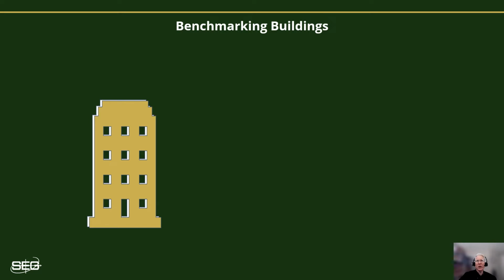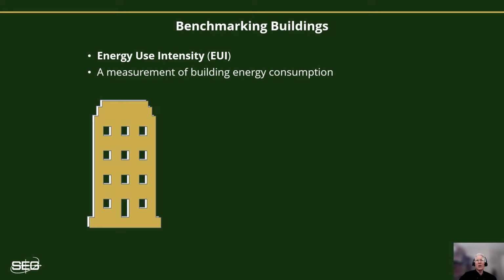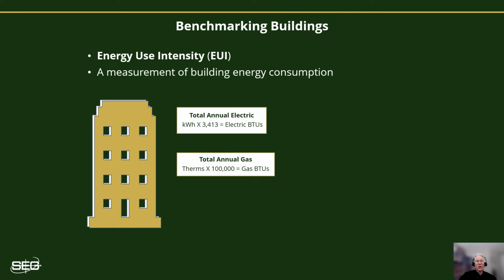Benchmarking all the buildings in your portfolio is a good way to compare a building's consumption rate against other similar types of buildings. To benchmark, we typically use a measurement called the Energy Use Intensity Value, or EUI. This provides us with a single common value for each building that makes it easier to compare them to one another. Calculating the EUI is a simple procedure. You'll want to gather your annual consumption for electricity and natural gas first. First, convert the building's electricity and natural gas into a common unit, the British thermal unit. Multiply your annual kilowatt hours by 3,413. Multiply your annual gas usage by 100,000.